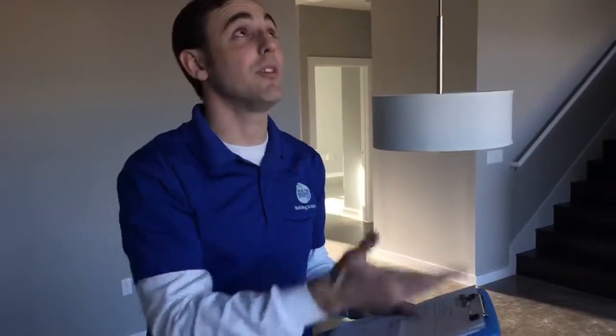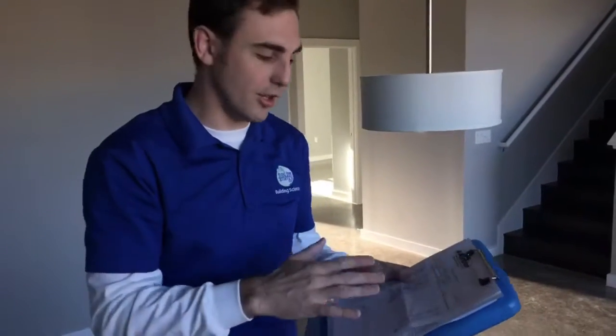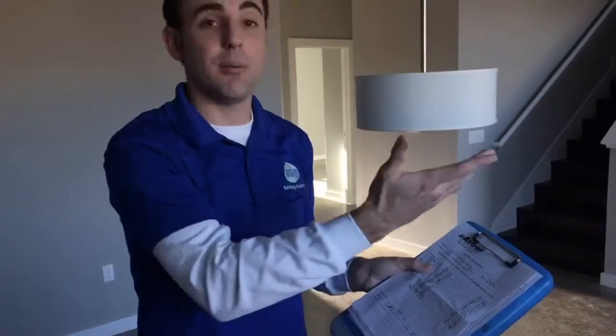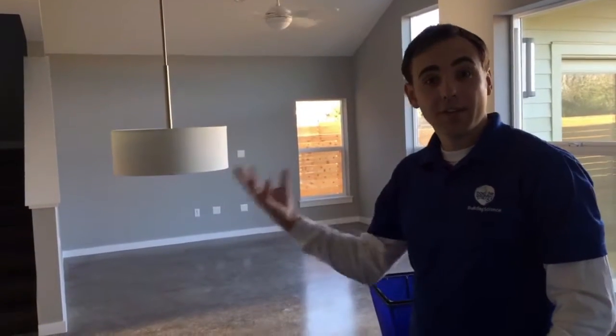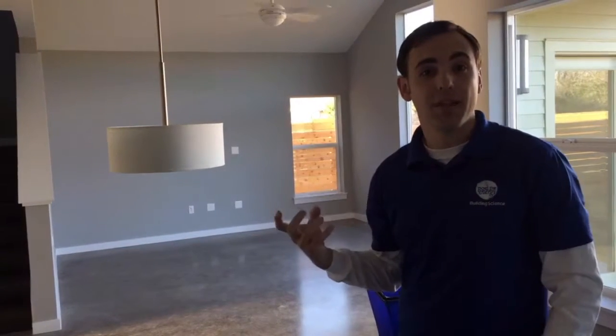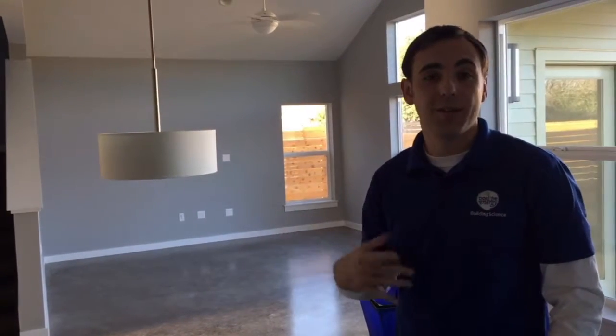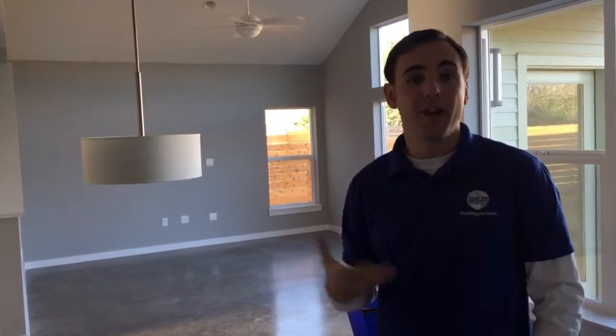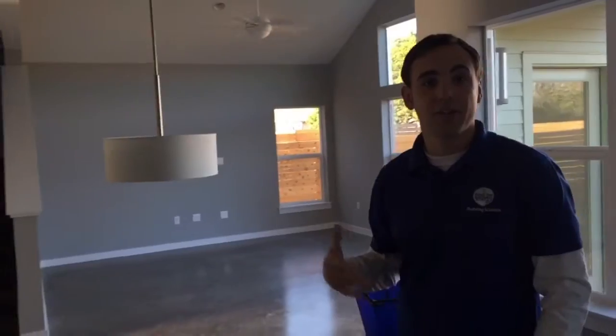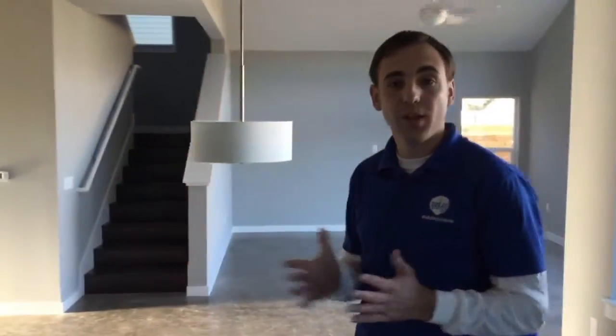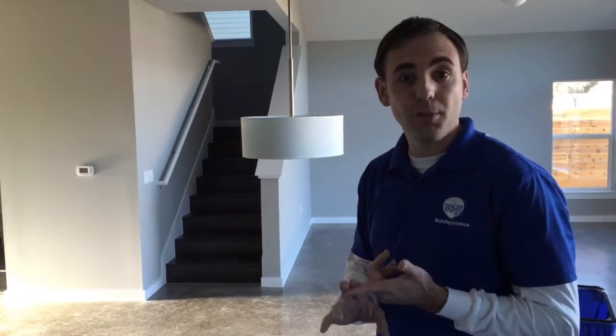So now that we've taken a look and we've seen the amount of CFM coming out of the register, I look at their test and balance sheet to make sure that that number, 47 CFM, is within 20% of the Manual J, and it's close to what the HVAC contractor got, which is correct. I then go around the rest of the house and I measure all of the airflows. I add up everything and make sure that the airflow for the whole house is within 10% of the Manual J. Codes may vary in your neck of the woods, but here in Austin, you need to be within 20% of individual airflows and 10% overall. Going around and measuring all the registers, I'm then going to check for noisy registers, vents that might be getting too much airflow, and I'm also going to check for registers that are cut off, that are not getting enough airflow.